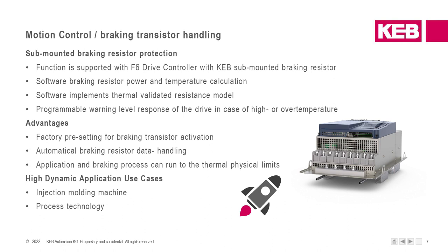How does it work? We have implemented a function, and this function is valid for the KEB COMBIVERT F6 drives with sub-mounted braking resistors. And internally, we have got a software where we can calculate the power and the temperature inside our KEB control board software. The software implements a thermal validated resistance model of the resistor and different warning levels, or the response of the warning levels and the temperature can be characterized by parameters.